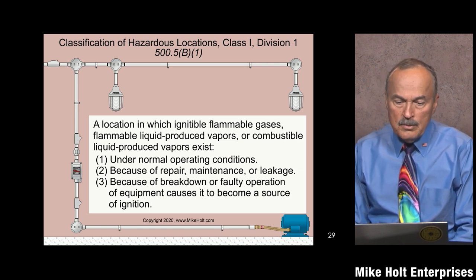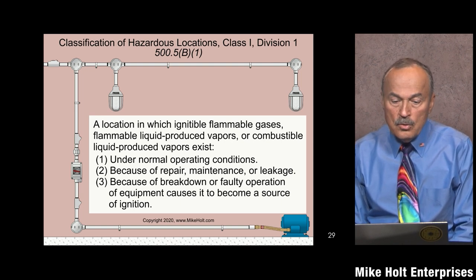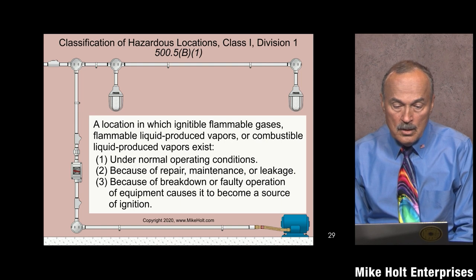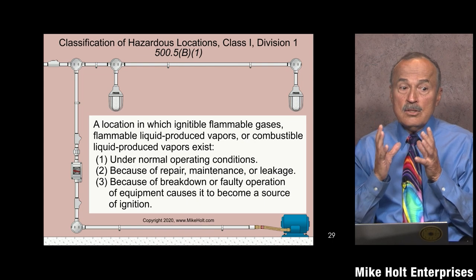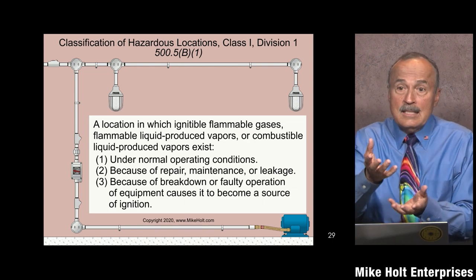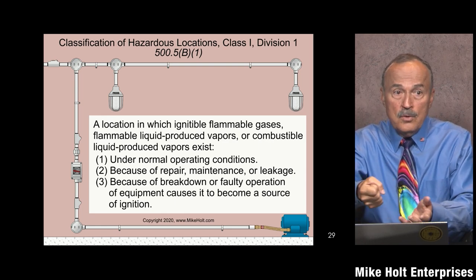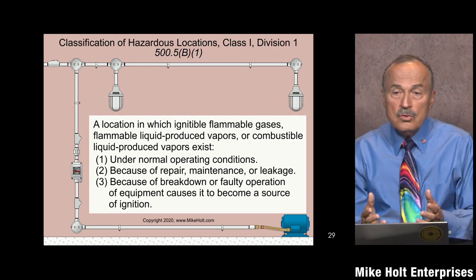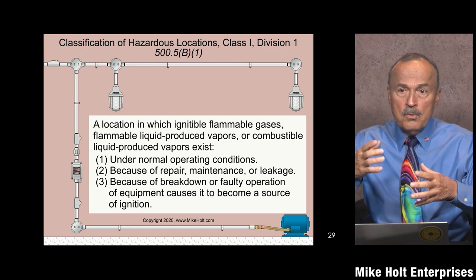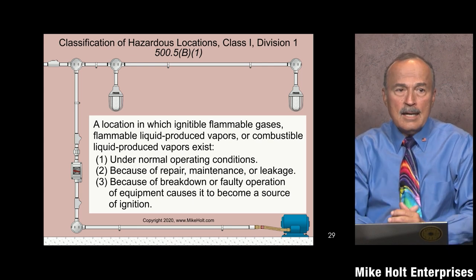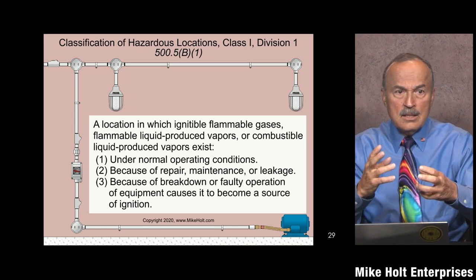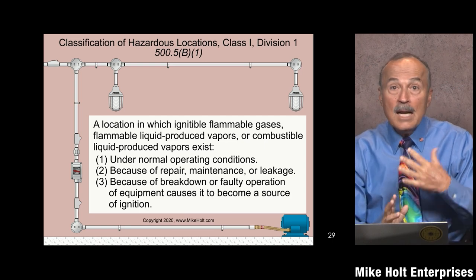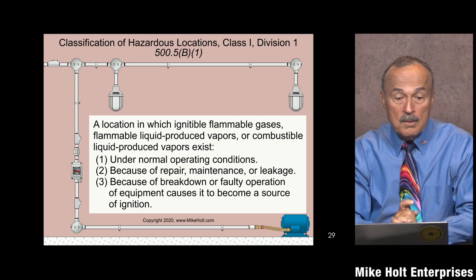Class 1 Division 1 is a location where ignitable flammable gases, liquid-produced vapors, or combustible liquids exist under normal operating conditions, or because of repair, maintenance, leakage, or equipment fault. For example, a gasoline dispenser — fuel is right there normally. Or maybe you're transporting propane tanks and something could fall and get damaged. Process engineers determine the classification, not the electrician.